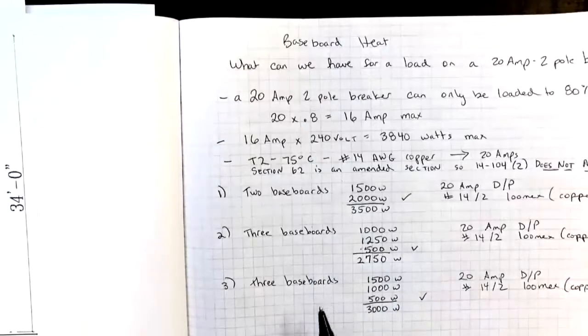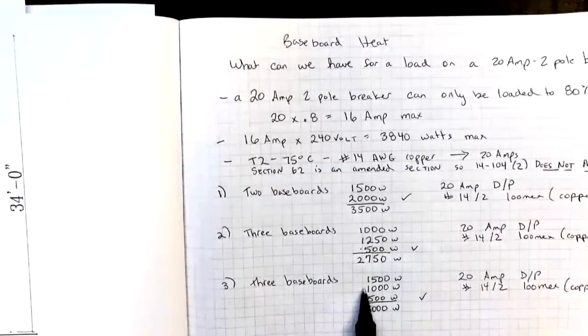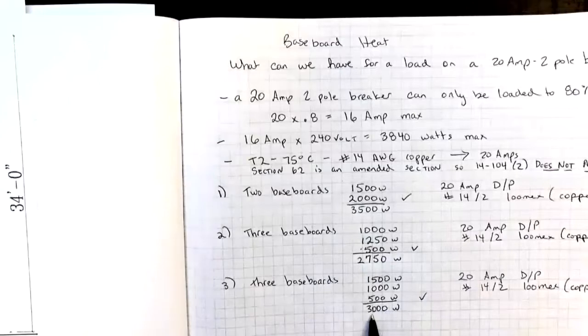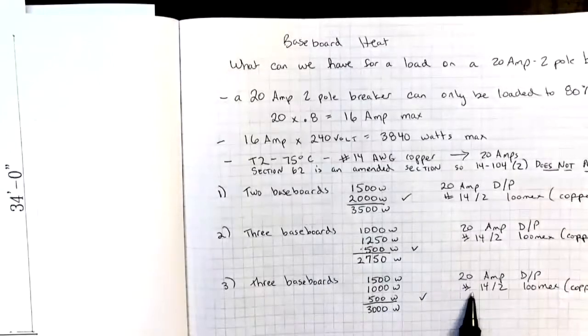Our third example was the three baseboards. This was in the master bedroom, the 1500 watt and the 1000 watt. And in the bathroom, we had a 500 watt. Adds up to 3000. So again, we can use a 20 amp double pole breaker and number 14 Loomex.